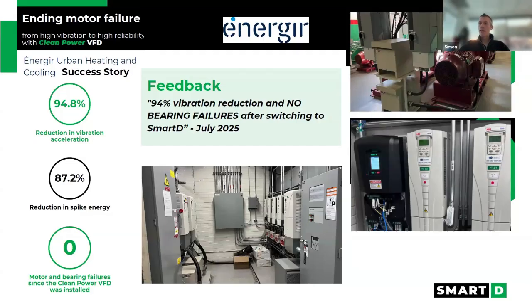But more importantly, they've stopped having those bearing issues. So we really see how we can go from the lab to the field, and we're seeing in the field the same benefits as what we see in the lab when we compare a clean power VFD, a standard drive, and a drive with filters.